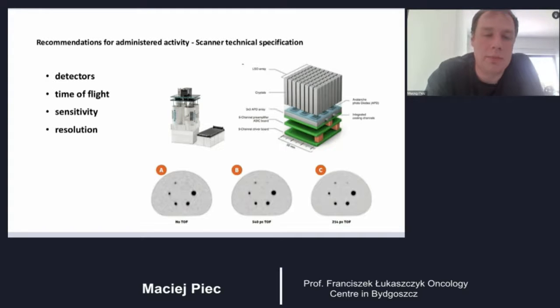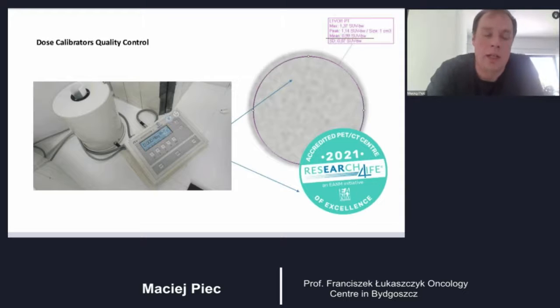And for new equipment, for example, made by Siemens, such as the Vision, which has semiconductor detectors, the crystal is smaller, sensitivity is higher, and the manufacturer declares that the sensitivity is higher by 20-25%. So we can try and reduce the dose administered to the patient. And I think it would be sensible to do it gradually. But from the manufacturer's declaration, we can reduce it further by an additional 20%. So this is another aspect that should be considered when we calculate the dose for an individual patient.